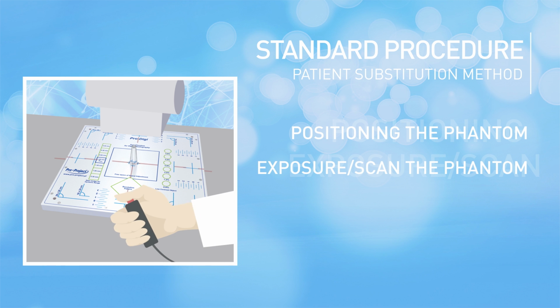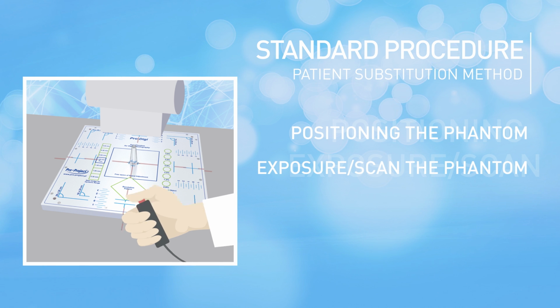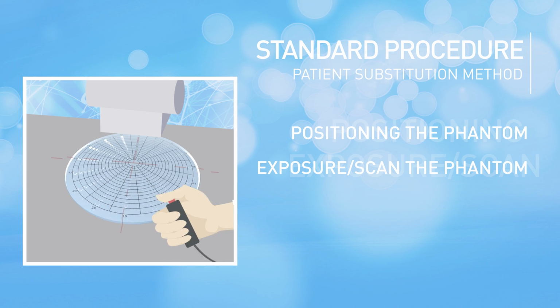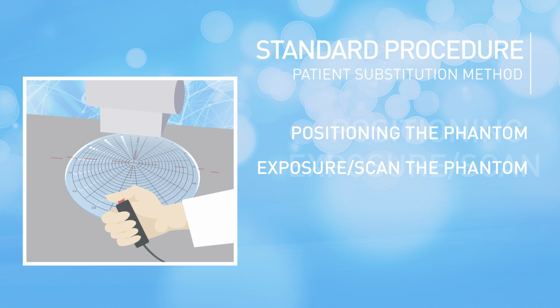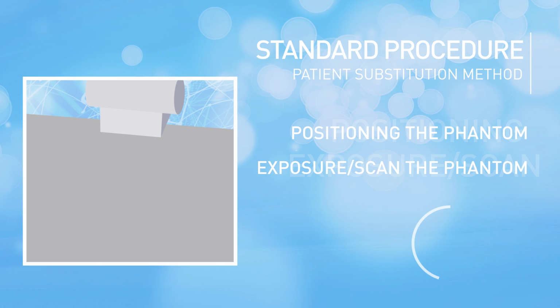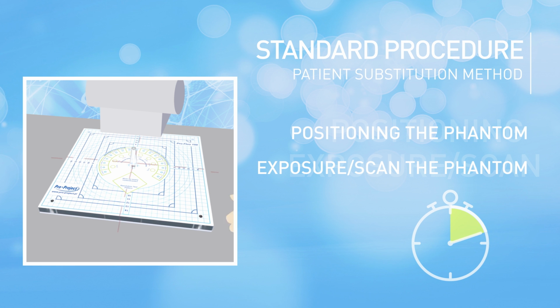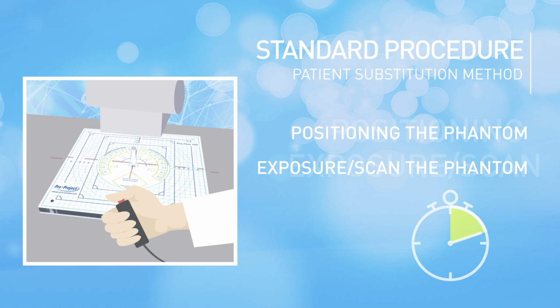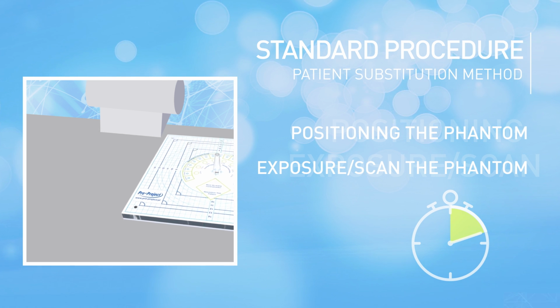Then you make an exposure or scan the phantom, depending on the apparatus type. Here we help you by providing combined many-in-one phantoms for each modality, designed to make it easy to position them and perform most, if not all, tests in a single exposure or scan. Apart from this, there is little that can be done to improve timing—it is just a physical job that must be done.